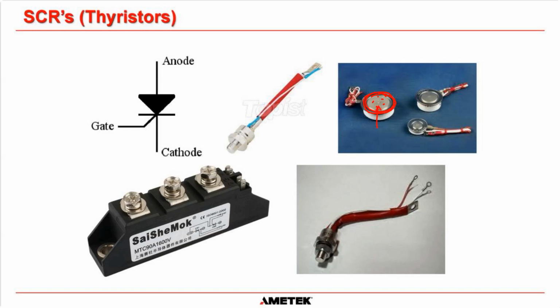You tend to find that if somebody has replaced an SCR mounted on a heatsink that should have copper grease, and they put thermal compound on it instead, it fails very quickly, because the surface area actually conducting is very small indeed.